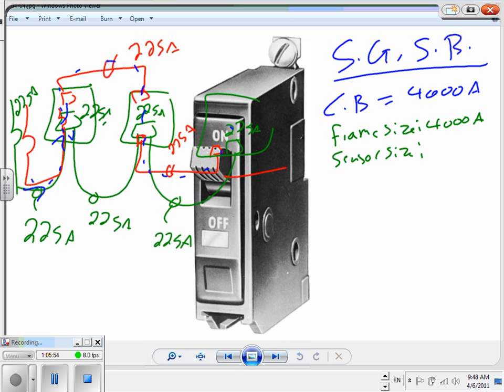It's the CT. They have CTs, guys, with the circuit breaker. What size CT do you want to put in the circuit breaker? So I have a 4,000 amp. You know what? My load is actually, I'm going to put a 3,000 amp sensor on this one. Now I'm limiting a physical space of 4,000 to a sensing of 3,000. That's my sensing. I'm sensing at 3,000.